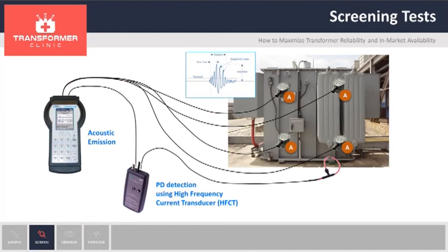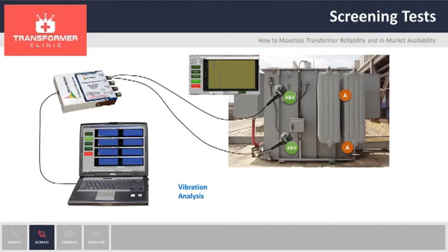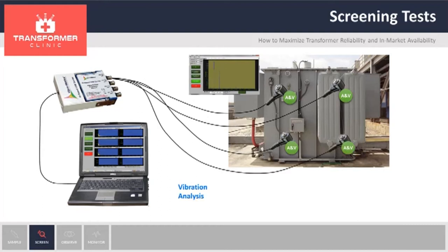Along with acoustic emission, the next test will be vibration. Vibration is used to look for mechanical defects. We can look at loose components on the transformer, loose core clamping or loose shifting, for example. We also take measurements at different points, and at the end, we have a layout showing all the measurements. We know where we took the measurements and can compare that over time.